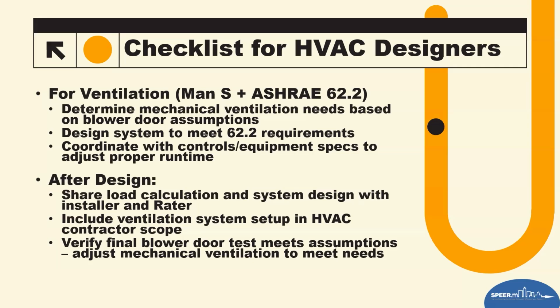They don't make a system that's sized in increments small enough to meet it dead on. But let's say your sizing came in at a 3.8 requirement and you sized it for a 3.5. That's not going to be detrimental. That's probably for the best, because you'll have longer run times and smaller equipment means less construction costs. But if you're saying that your assumption is 3.8 for the sizing, and your blower door is now closer to 5, and you were trying to hit 4 to get that sizing to 3.8, and now it's off and you're looking at closer to a 4. And if someone just says, just put a 4 on there and oversize it, now we've got oversized equipment, which means short cycling of the equipment and higher humidity than normal.